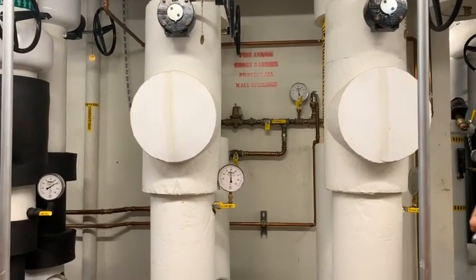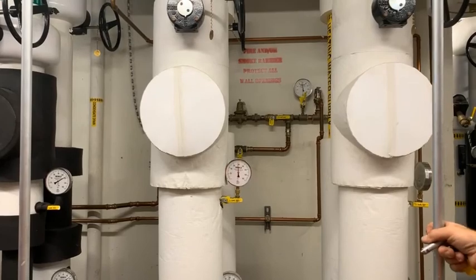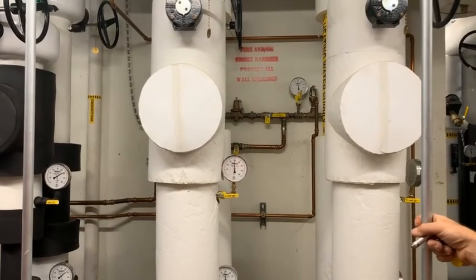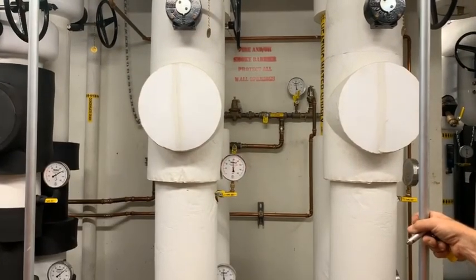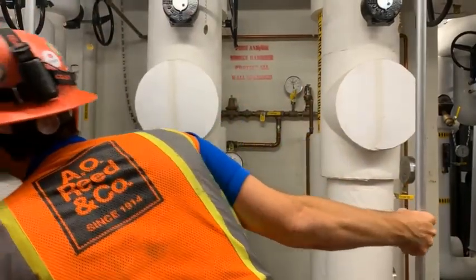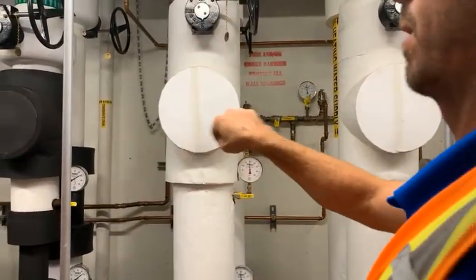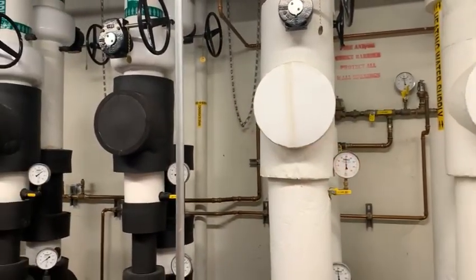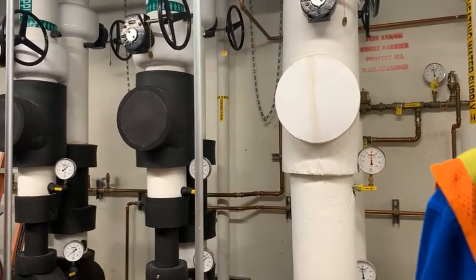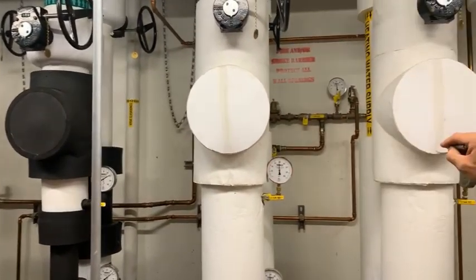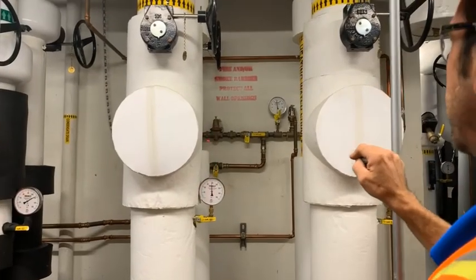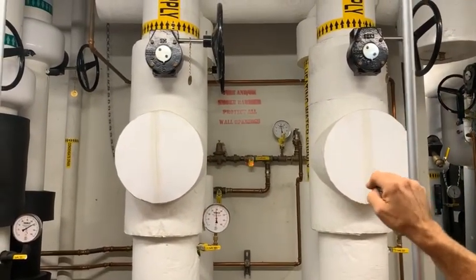What's our inlet pressure? It should be 80. 80? Yeah, because we're on the same level as the main pressure reducing valve down there. As it's flowing water, there could be a little pressure drop through that backflow that's in front of it. Make sure this bypass valve is closed. We want the 2 upper valves open at all times.